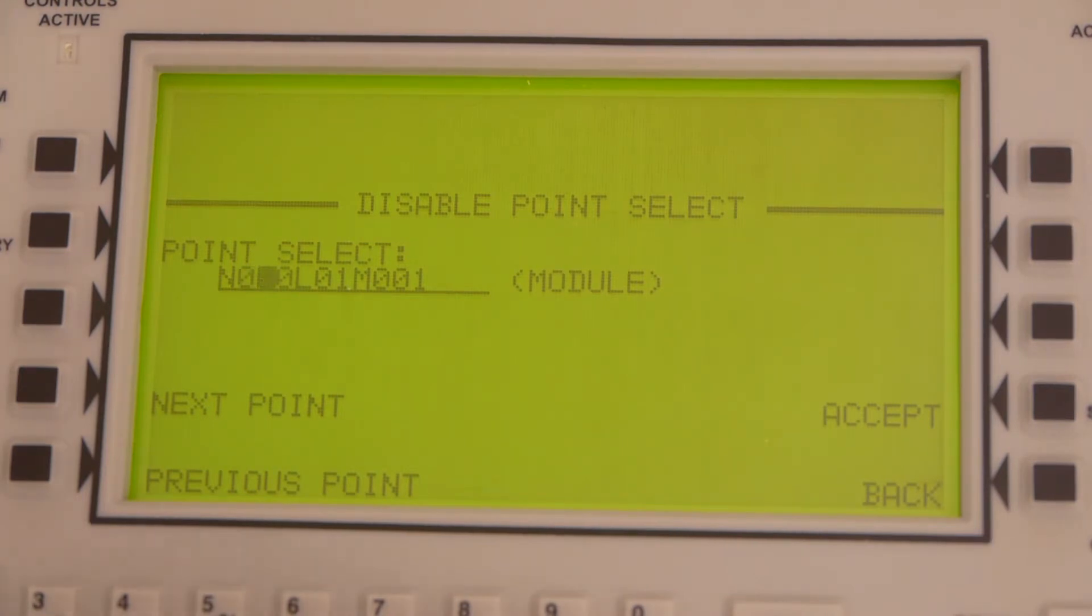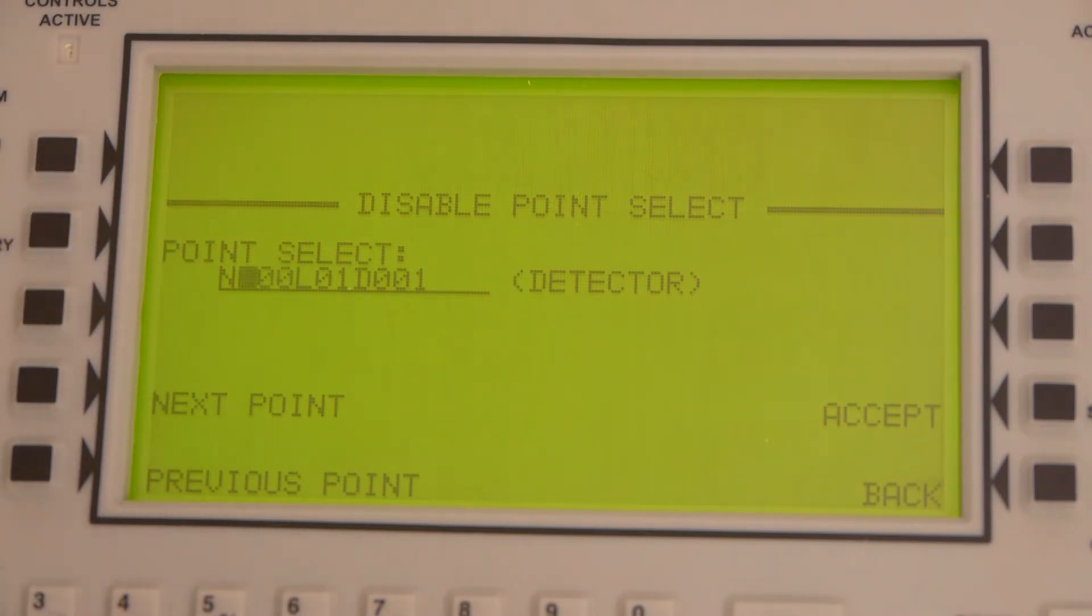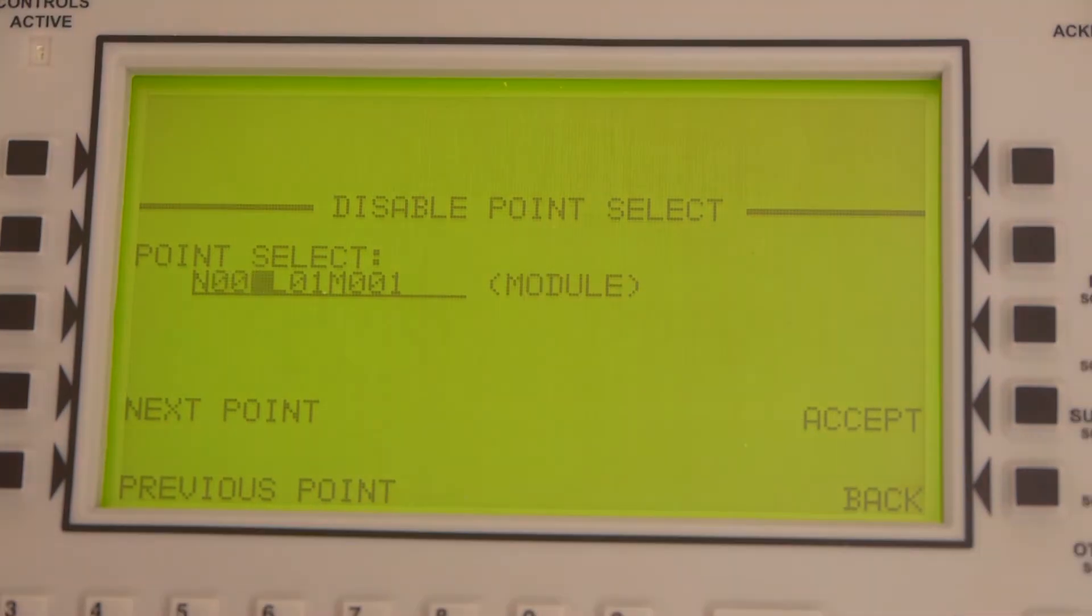Next, you're going to figure out what node it is. If you're on a system without a DVC or enunciator or other panels, and there's nothing plugged into the NUP port, then your panel is probably node zero. If you have a cable plugged into the NUP port or there's a DVC or enunciator, then it's going to be something other than zero. There's no way to really know what node it is. You kind of have to know how the system was designed. It might say on the door or on the keypad, or it might even be programmed on the main display. In my case, this is node number one.